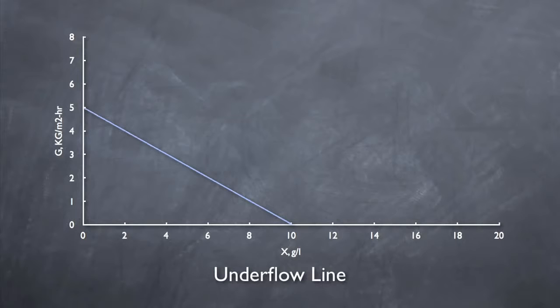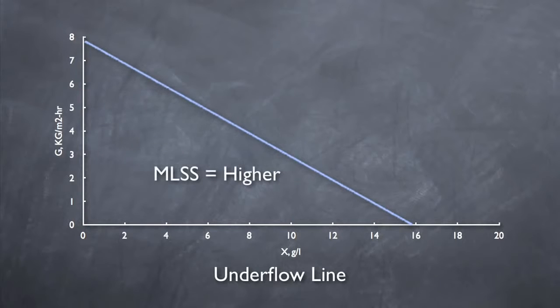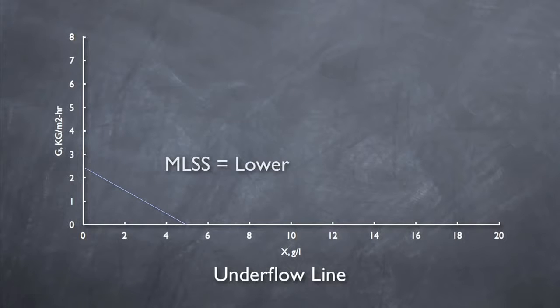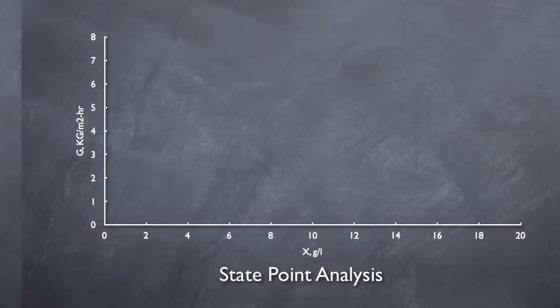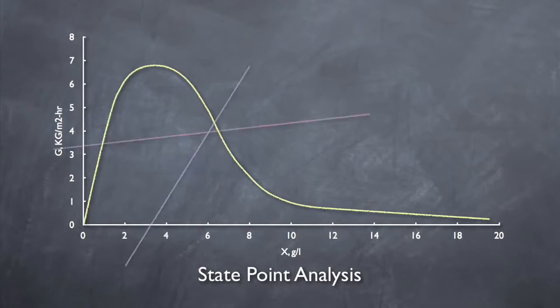Also, the location of this line can be adjusted by changing the solids concentration entering the clarifier. A higher concentration moves the line away from the origin, with the opposite occurring with a lower concentration.